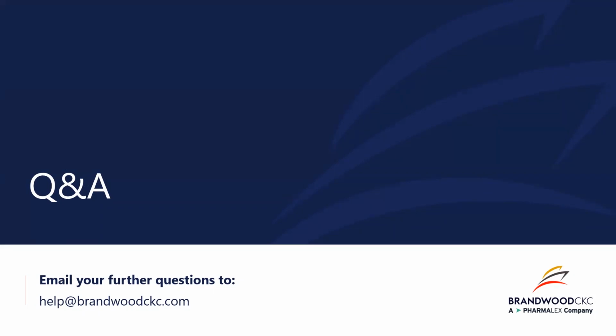Question 2, how many risk documents are expected? Risk plan, FMEA, production FMEA, list of harms, hazard table, etc. Where does it end? A common question, actually. There are no specific requirements on the number of documents, nor the structure of the documentation. ISO 14971 does require a risk management plan and a risk management report. Then remains the hazard analysis, risk analysis, etc., which can be a single document or multiple documents. The structure and the number of documents is at the discretion of the manufacturer.